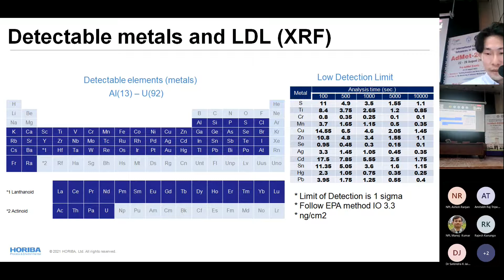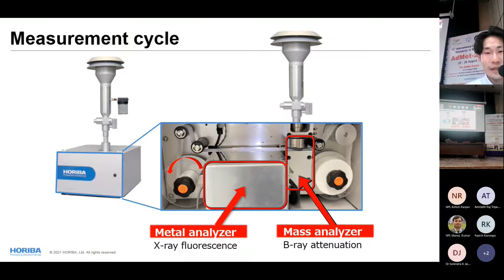Since this instrument is composed of two technologies, XRF and beta ray attenuation, sometimes it's hard for people to imagine how it works. So this is the internal image. From the sampling head, we inhale the sample particles, and the filter tape captures them. At the same position, mass concentration analysis is completed with the beta ray attenuation technology. And now with the roller, the orange bar, the filter tape is advanced to the X-ray analysis position. In this procedure, the measurement of two different parameters is completed. We actually have a booth and the actual instrument in the other building. So if you have time later, please visit us and have a chat there.